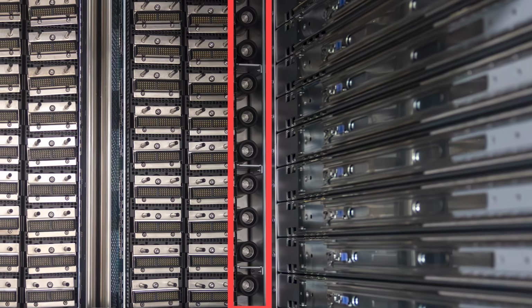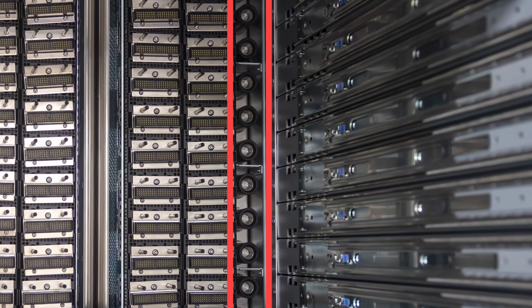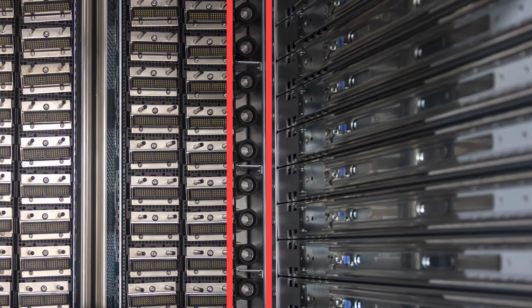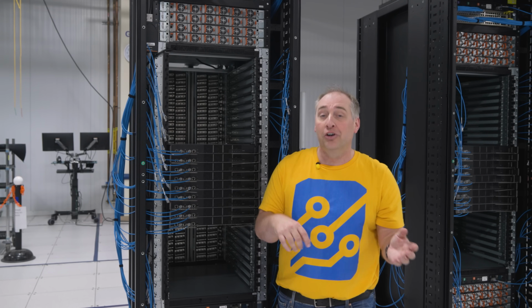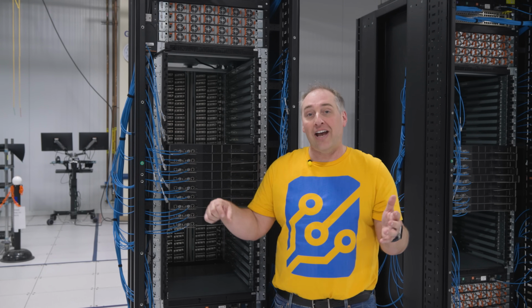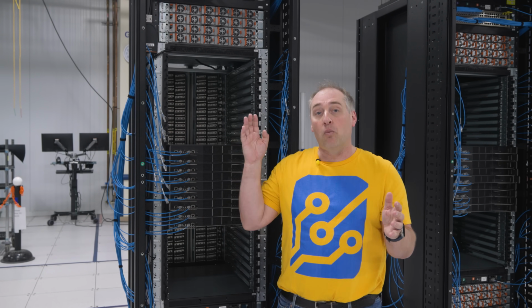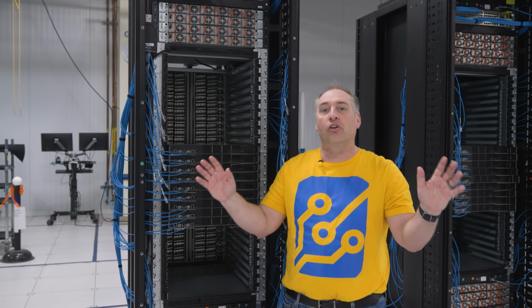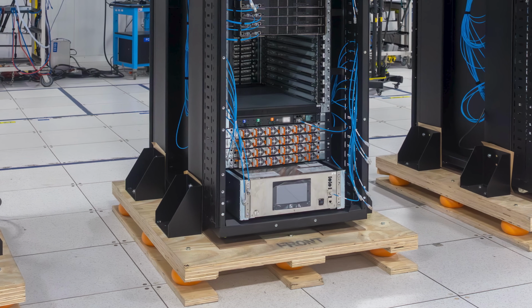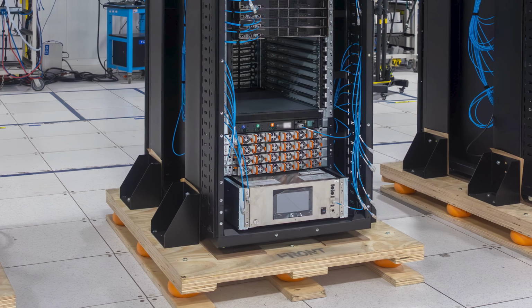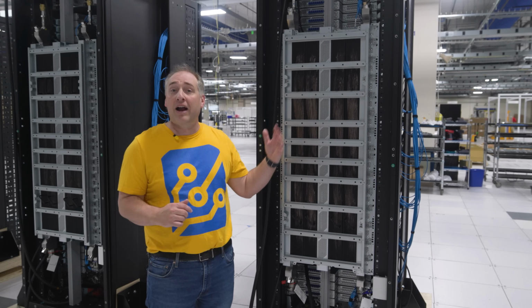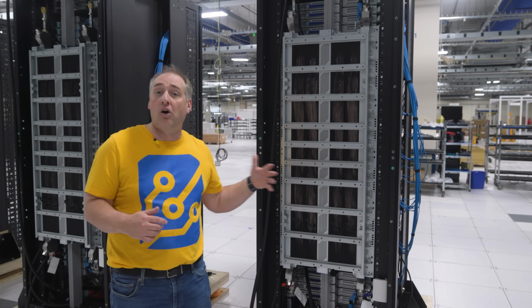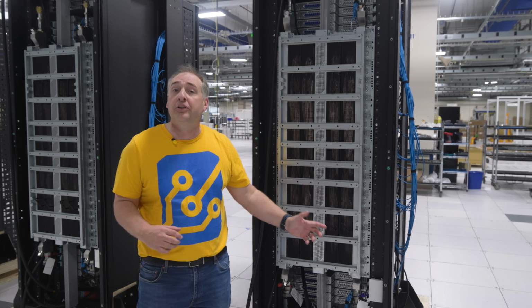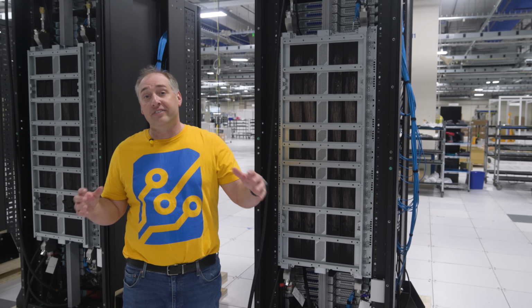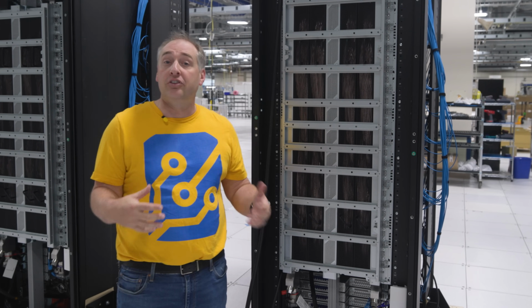Of course, the cool liquid comes in. It's then warmed by the components inside, either the NVLink switches or the compute nodes. And then as it exits the chassis in the rear, it goes to that warm side and then it is exchanged through the facility. And the CDU down below, or the coolant distribution unit, is really there to make sure that all of the fluid in the rack manages to circulate through all of the nodes, but then also the fluid can be exchanged with the facility water, and that allows you to efficiently cool the rack.